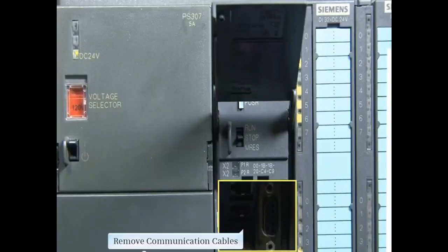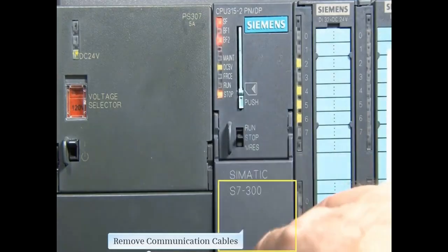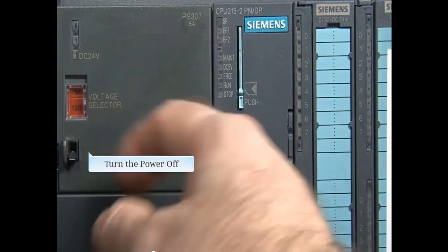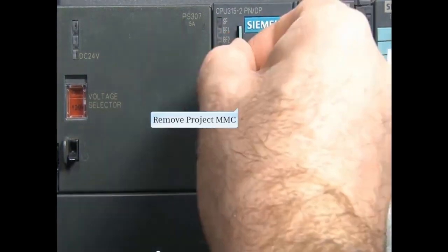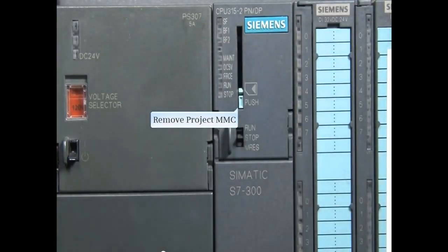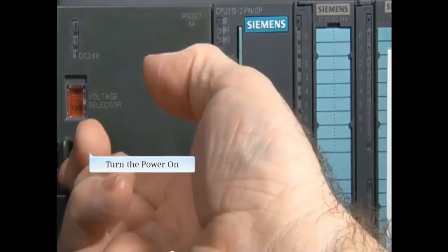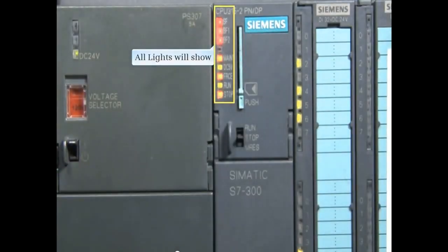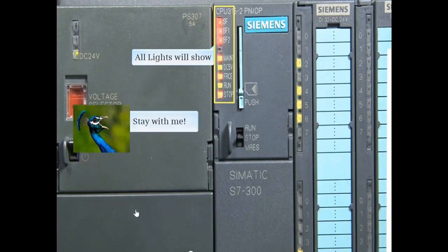With the CPU in the stop mode, remove the communication cables, turn the CPU off, and remove the project micro memory card. Replace it with the firmware memory card. Then turn the power on. All the lights will illuminate and stay on for about 16 seconds or so. I know this part isn't too exciting, but hang in there with me a little while longer.